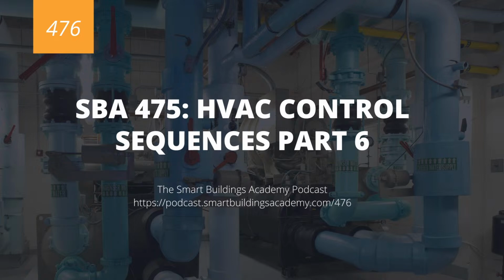All these concepts, you have to understand first that we're utilizing refrigerant, and we are transferring BTUs from that refrigerant to another water source. So in this case, we have a chilled water source. It is transferring the BTUs to the refrigerant, and then the refrigerant is transferring those BTUs back to the condenser water source, which then goes out to cooling towers, which transfers the BTUs to the ambient air, typically using evaporation.